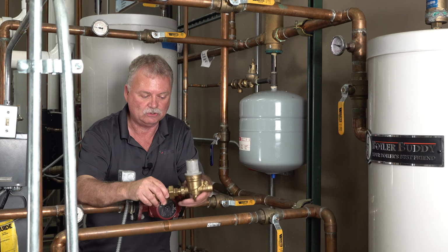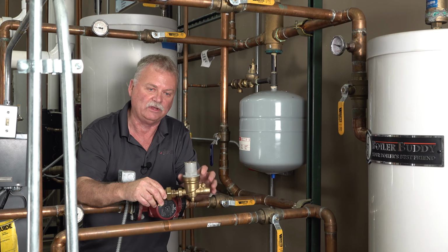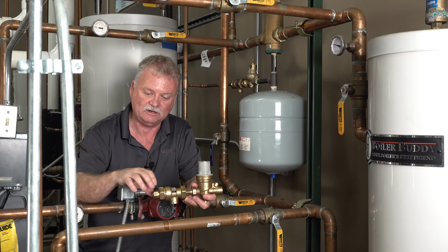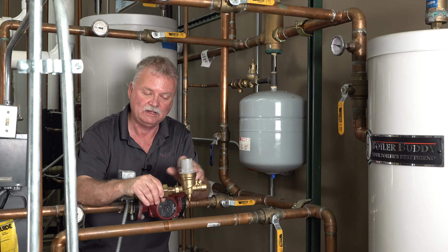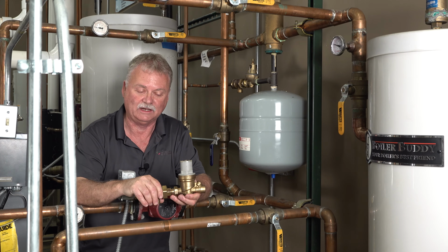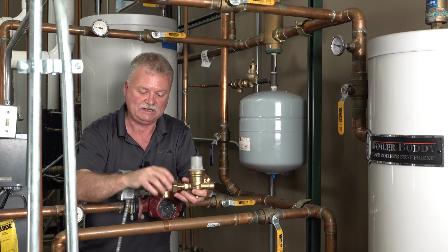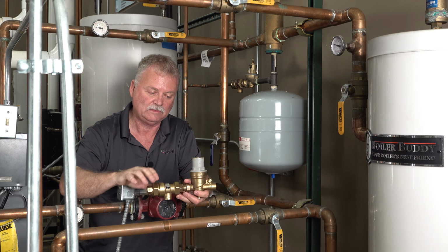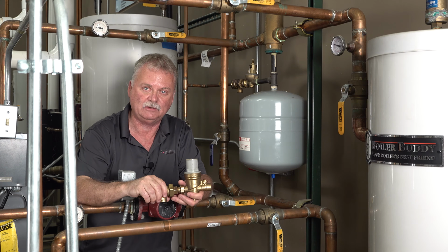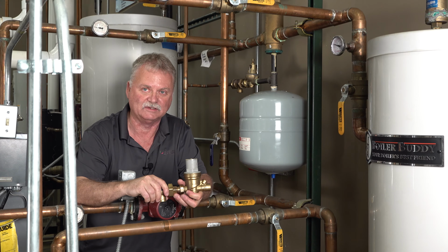If we let that water directly into our boiler system that's running at 12 psi with a 30-pound relief valve on the boiler, and I've got 40 pounds over here and no valve here, that water's going to go right out through my relief valve, and we don't want that. So we need a PRV, or pressure reducing valve, to take this high pressure water, reduce it down to about 12 to 15 pounds, which is what a typical hydronic heating system residentially and light commercially runs at.